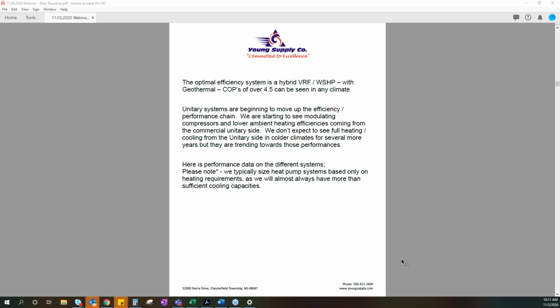And then we have an optimal system, which is a VRF with water source. Typically our COPs are 4.5 in any climate. It really doesn't matter what the outside temperature is, doesn't matter what's going on. When we have a water source VRF system, our COPs are over 4.5, and I've seen as much as 5.2. So again, for every dollar that goes in, you get $5 worth of heat out.